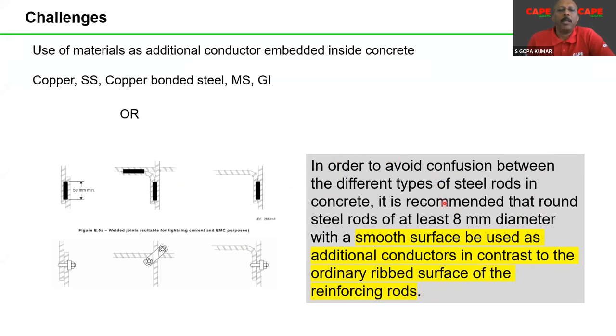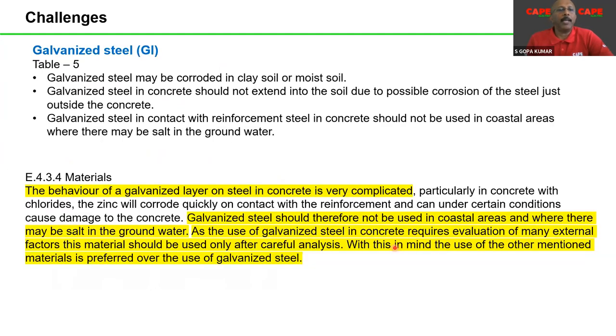So please read, it is recommended. If the word recommended is used in a standard, that means the standard is recommending to use it. The standard is recommending you can use the rebar, but it is recommending a conductor with a smooth surface. That means a conductor of copper, stainless steel, or whatever the material, with a smooth surface as an additional conductor in the concrete is recommended in the standard, which is preferred more than the ribbed material.